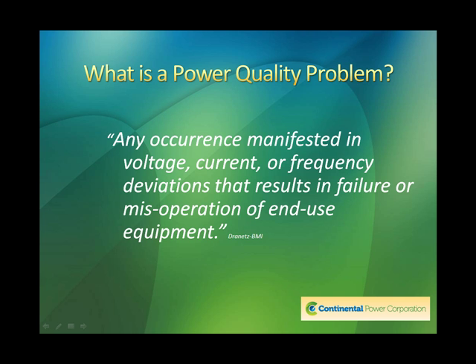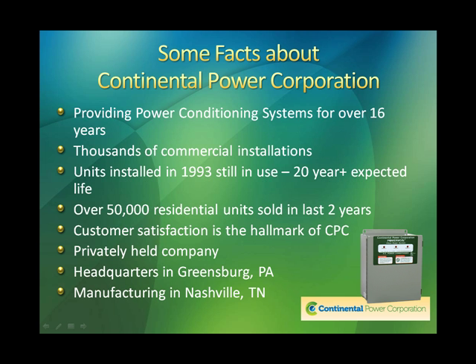According to IEEE, a power quality problem is any occurrence manifested in voltage, current, or frequency deviations that result in failure or misoperation of end-use equipment. So it's not just a disruption of voltage. It can be a disruption in the way that the voltage is being used, and it would therefore manifest itself in current. Or it can distort the frequency and cause deviations. So it's a whole host of things that we have to be aware of to understand why we have power quality problems.